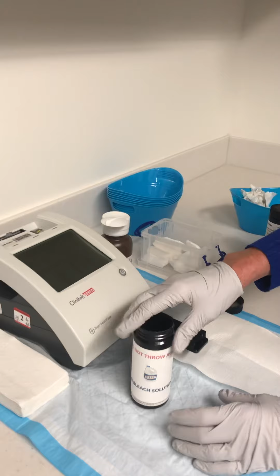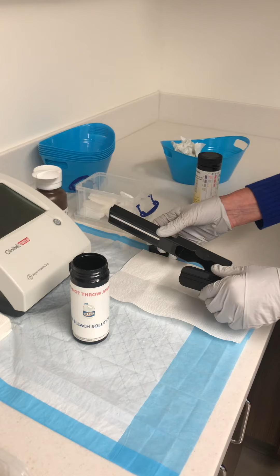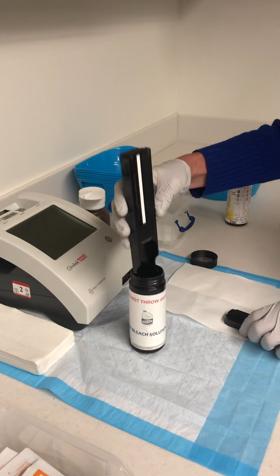What you want to do is prepare a fresh bleach solution. You remove the test table from the analyzer, and if there's any urine in there, you'd want to drain it. And we would do the cleaning that I just demonstrated with the Q-tip and then rinsing it off. Then we want to place the test table inside this 4 inches of bleach solution, and we soak it for 2 to 10 minutes, but no more than 10 minutes.